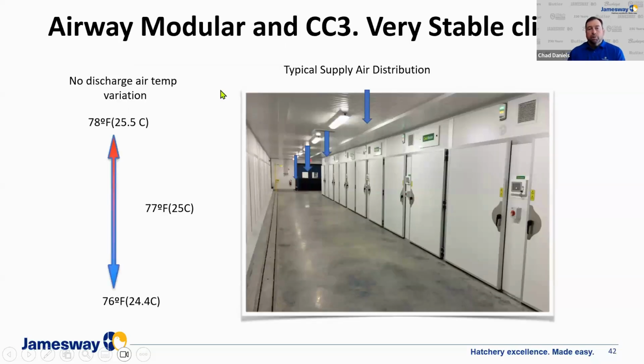So when we look at both of those types of systems, the Airway Modular and the CC3, we recognize that because we're controlling the temperature of the air being discharged into the room, the room can have that drop ceiling, you can have a very small space, and because that temperature variation is gone, you're controlling the temperature in this environment very precisely in order to meet the needs of the incubation equipment. So it makes for a very clean installation, and it's very easy to control.